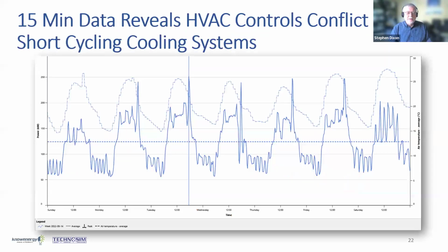Going beyond that, digging down to every 15 minutes, we found a chiller that was cycling unnecessarily. This is a week in the life of a building. The dotted line is the temperature, and you can see this chiller cycling at night. One problem was that the controls on the chiller weren't working.